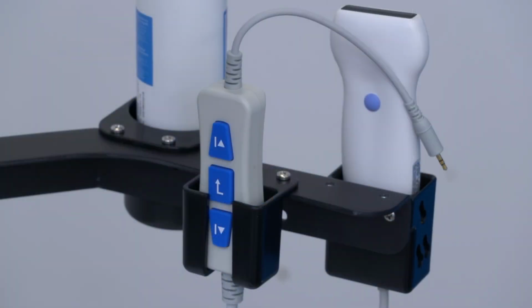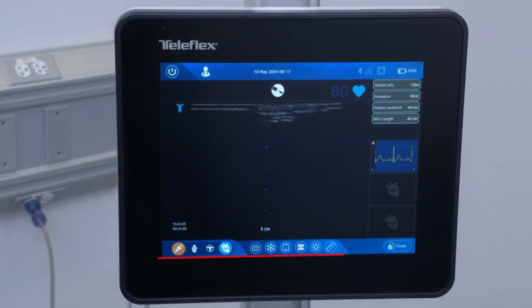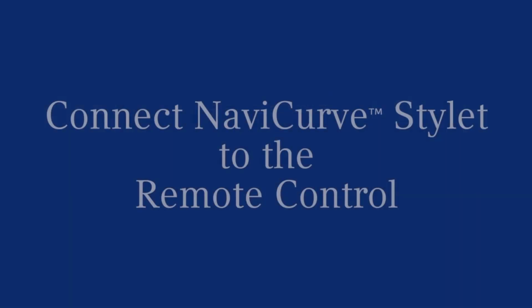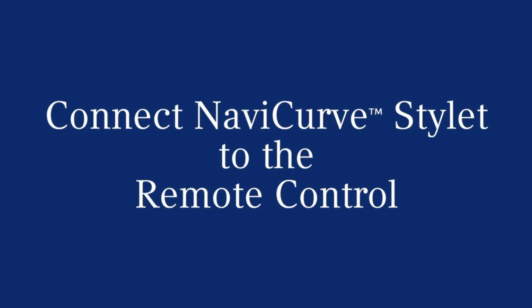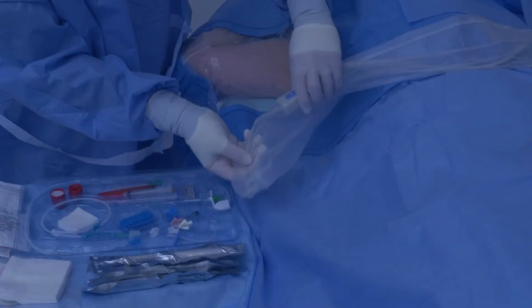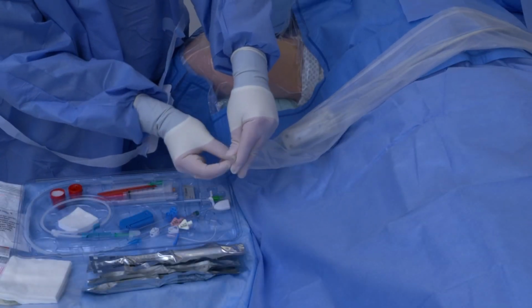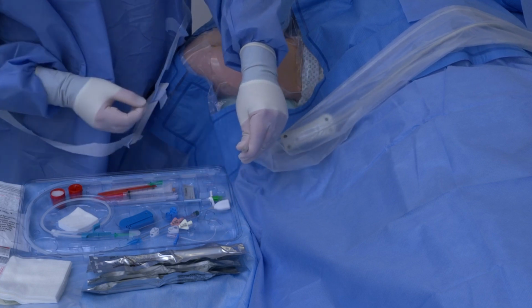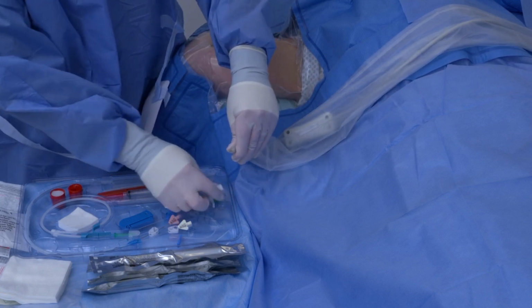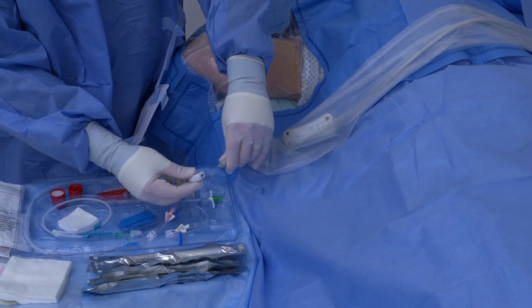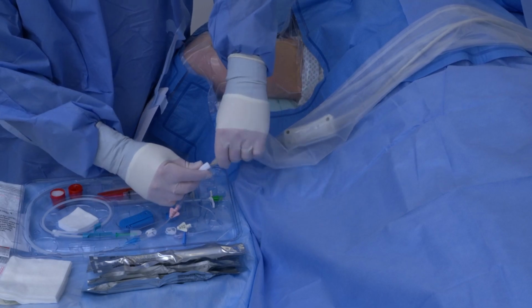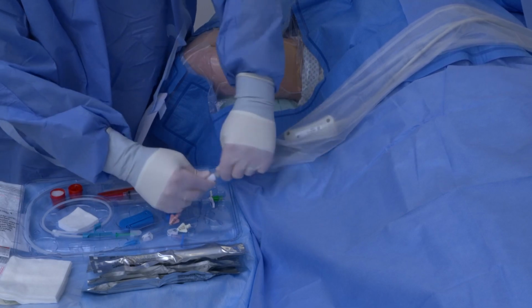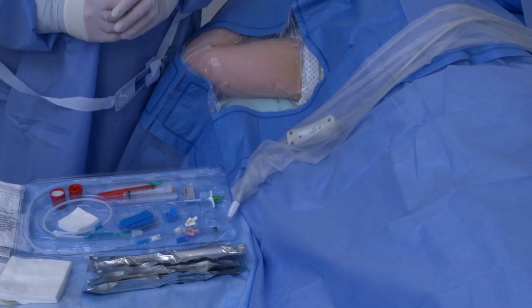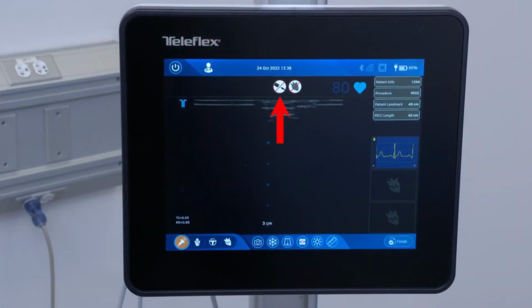The remote control has left, enter, and right buttons to toggle through the icons along the bottom of the screen. Pull the sterile sleeve tightly over the tip of the remote control cable plug without piercing the plastic. While maintaining the sterile field, carefully insert the remote control plug into the NaviCurve stylet jack and twist slightly, piercing the sterile sleeve. Verify the stylet disconnected icon stops flashing at the top of the monitor screen and disappears.